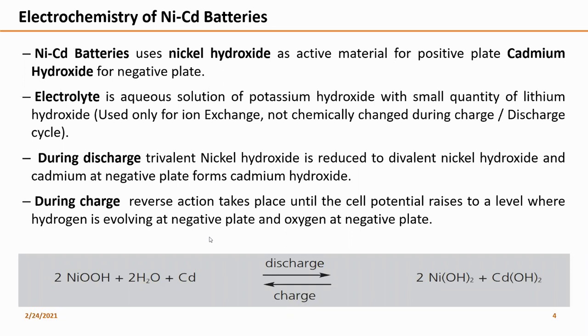There is no change in electrolyte level because during charge or discharge, it neither delivers nor consumes water significantly. If we charge the battery per manufacturer specification or charge cycle, there will not be much chemical reaction or electrolyte consumption in nickel cadmium. That is a major advantage.